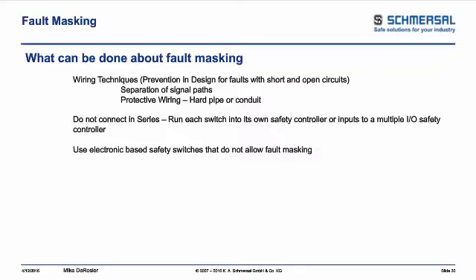Now, whether they got indemnification or they just put it in because of the request that allows them to bypass those guard doors, sometimes they're there because it might be not an operator bypass, but it's designed to be a maintenance override. But unfortunately, they just jump around the safety devices without taking into consideration forcing it into a jog or an inching mode and monitoring the speed of that function to reduce the risk for maintenance setup, for example, or a changeover to that point.